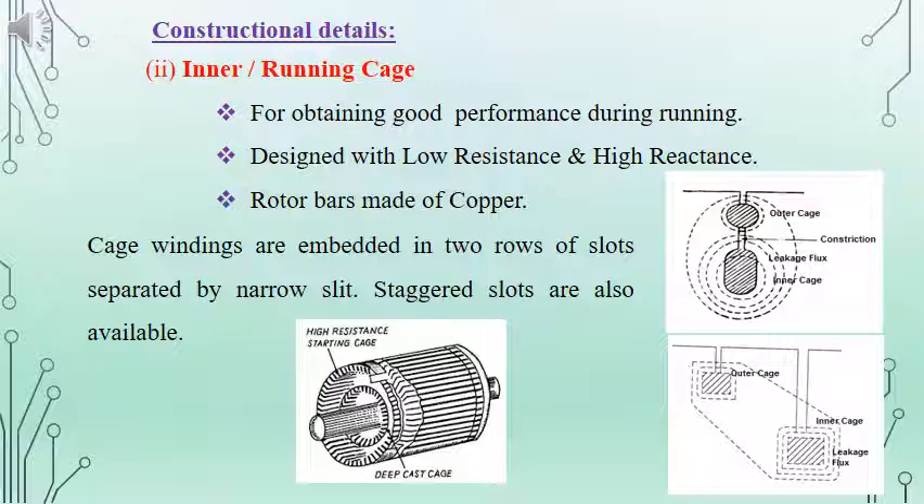In the figure we can see two different slots provided on the rotor. At the outer side of the core, we have a slot provided for the starting or outer cage. On the inner side, we have another slot with a larger area, which is meant for the inner or running cage. By increasing the area of cross-section for the inner or running cage, we can reduce the resistance. In between the inner slot and outer slot, there will be a narrow slit, and the slots can be staggered type. From the figure, the two types of slots and cages are clear.